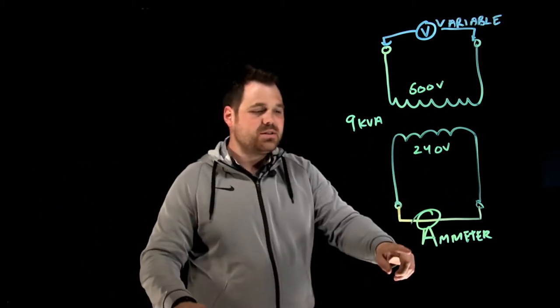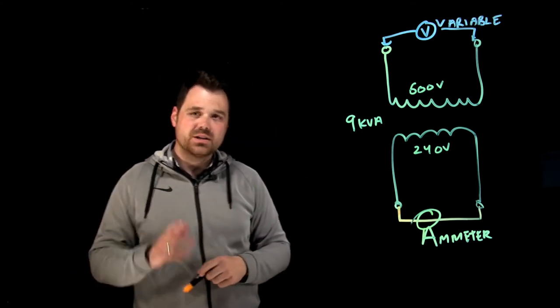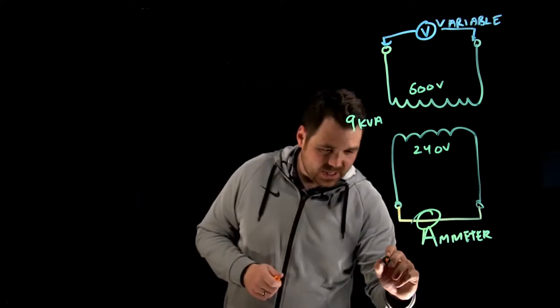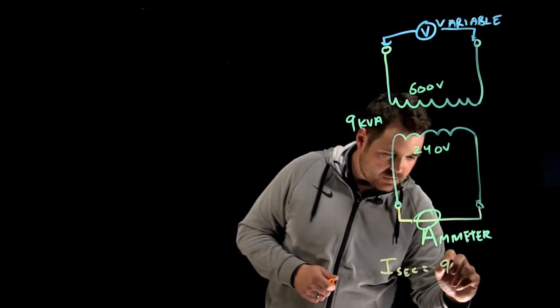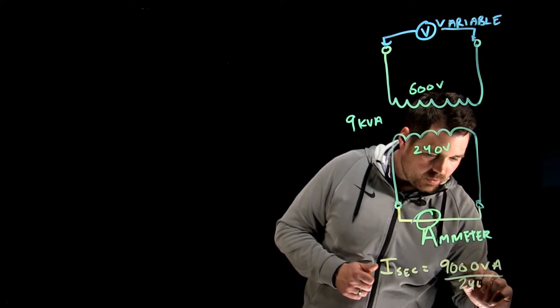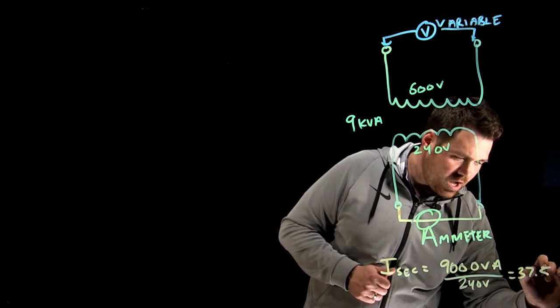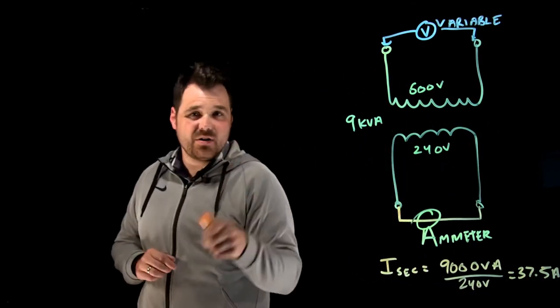So quick reminder, how do we calculate that? Well, I have my secondary would be 9,000 VA divided by 240 volts. So in this case, it gives us 37.5 amps. That's my rated secondary current.